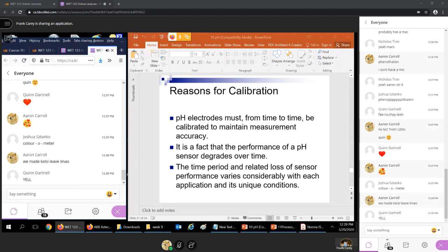Yeah, or softly though. Okay, obviously pH instruments must be calibrated. In the pharmaceutical industry, they do a 5-point calibration. And that's typical, just because they have to be deadly accurate. In many laboratories, they also will do a 5-point calibration. I've never done one. The common calibration for pH instruments is a 3-point calibration. They should be calibrated fairly regularly. Again, you just follow your standard operating procedures or the manual.